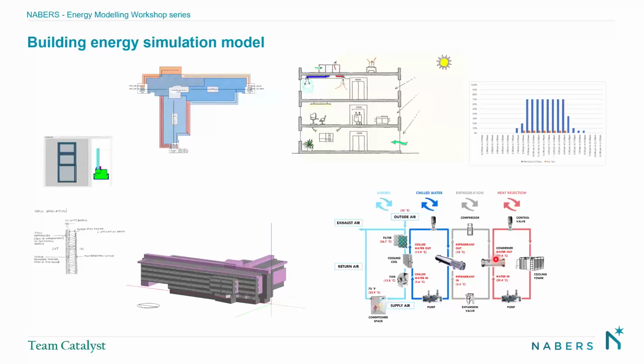From the condenser vessel, in this case a water-cooled system, there's a cooling tower. Condenser pumps push that water to the cooling tower. The cooling tower is essentially just a shower, a spray, and as the spray comes down, some of that water evaporates. Water has a very high latent heat capacity, so that cools the water in the cooling tower basin.